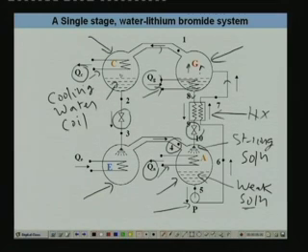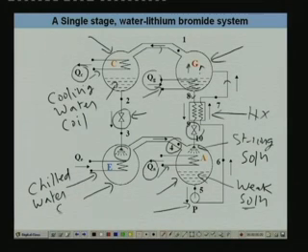This is still at high pressure, so the pressure has got to be reduced. So this water flows through this refrigerant expansion valve, where it undergoes pressure drop, and this low pressure water is now sprayed into this evaporator. When it is sprayed, the liquid droplets fall onto this chilled water coil. And as it falls on the chilled water coil, it evaporates.